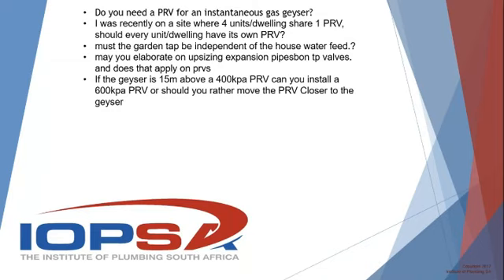Okay, if I can jump in there, that was part of last week's presentation also. Yes. Remember that for every meter, you're losing 10 kPa. So on 15 meters, you're going to be losing 150 kPa. Your valve is already only going to give you 300 kPa to set pressure, so you're only going to be getting about 150 kPa out, and that's before any friction losses in the pipe. So yeah, you shouldn't have it that far away. It would be much better to rather move the PRV closer.